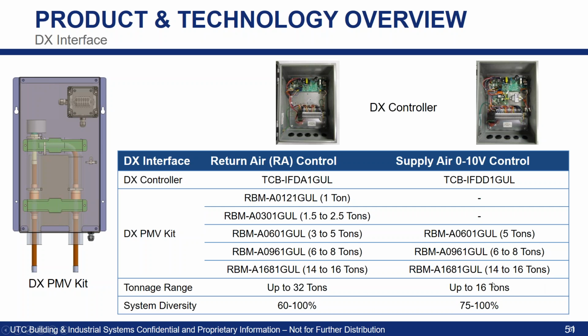Now, if you're wondering why there's a difference here, it all comes down to the control. If you're strictly looking for return air control, and we all know what systems run well off of return air and which ones don't, return air control, you're typically looking at large common spaces. That's where that control comes into play better. While looking for 0 to 10 volt control is more where you'd be getting into VAV systems, where you're controlling your systems off of supply air temp. You just need to remember that right now, as of today, we're limited to 16 tons if you were doing a VAV system, and 32 tons if you're more of a typical constant volume, staged air volume type system.